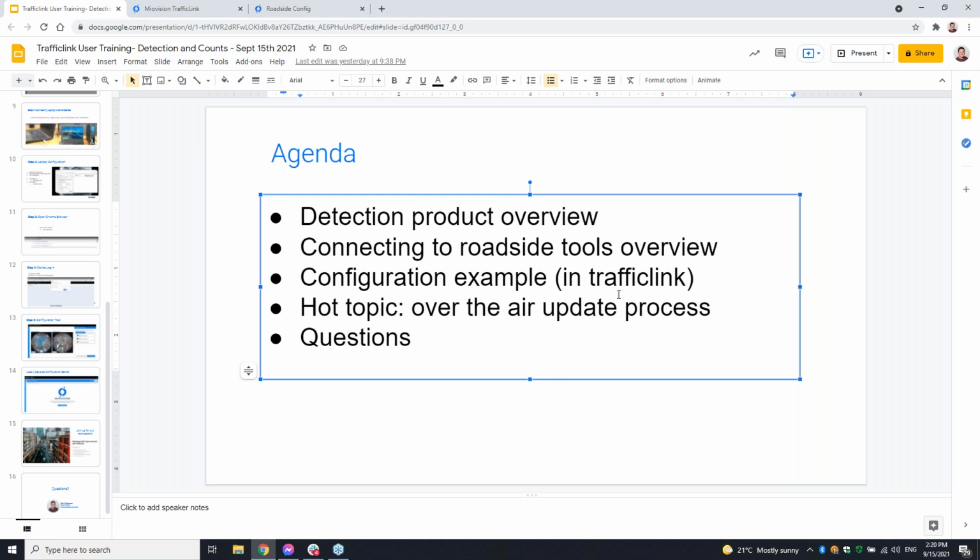It happens in 2 stages. It comes down to the device first, and then once it's a safe moment to do so, it'll automatically update itself. The process of updating takes about 90 seconds. During that period, the device will go into a constant call or a fail-safe recall, and it will continuously cycle the lights. As soon as operation comes back to normal, it'll come out of the fail-safe recall after the 90 seconds and go about its business.